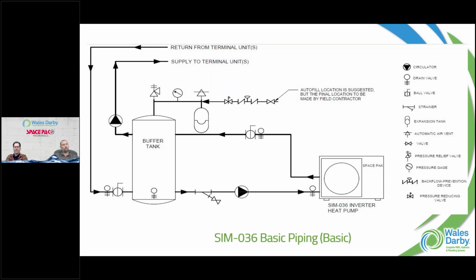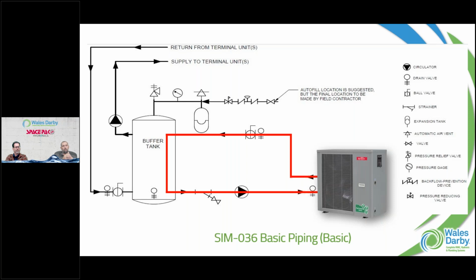So this slide kind of just gives you that breakdown of what a piping system looks like. And I like to treat it as two different systems, right? Because that buffer tank's gonna isolate it, it hydraulically separates the flows. But here's my outdoor circuit, right, so I'm worried about, I got some piping, an outdoor unit, a buffer tank, and a circulator.